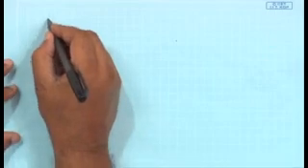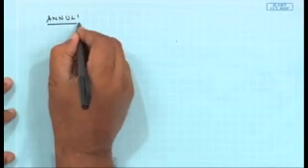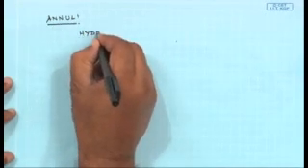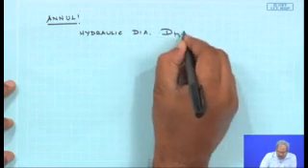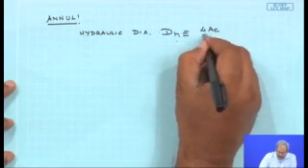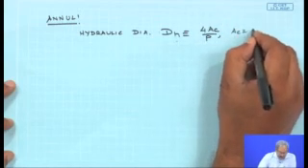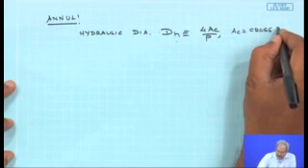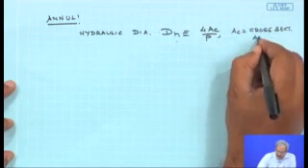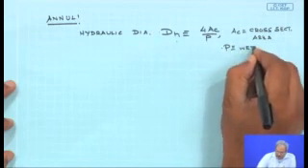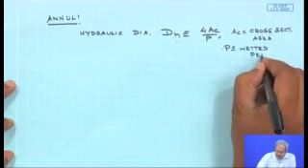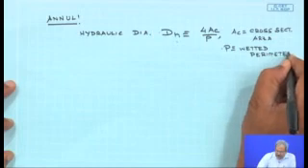So, in order to find the coefficient for the annuli, you find out the hydraulic diameter, which is d suffix h and is defined as 4 AC by P. AC is the cross sectional area for flow of the liquid and P is the wetted perimeter of the annular region.